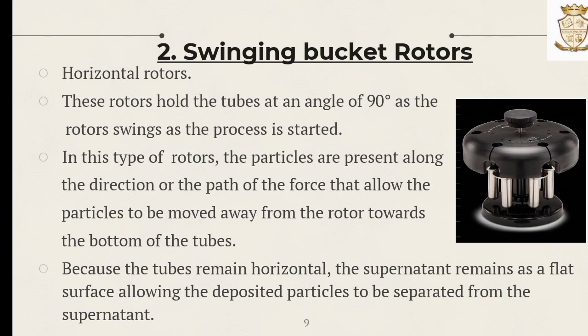The second one is the swinging bucket rotor, also known as horizontal rotors. These rotors hold the tube at an angle of 90 degrees as the rotor swings when the process is started. The particles move along the direction of the path of the force, allowing them to move away from the rotor towards the bottom of the tubes. Because the tube remains horizontal, the supernatant remains as a flat surface, allowing the deposited particles to be separated from the supernatant.